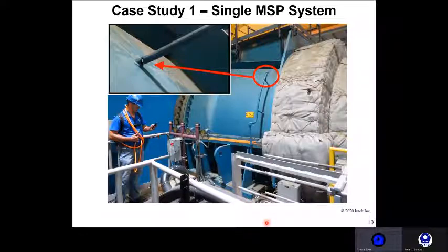The bottom line is that as a result of the testing we performed, this plant was able to mitigate 2 major sources of air in-leakage and avoid potential problems on multiple units because we were able to locate and quantify both sources, which turned out to be common issues on all of their units. This could not have been accomplished in such a short time without the use of the Re-Evac in conjunction with the helium detector.